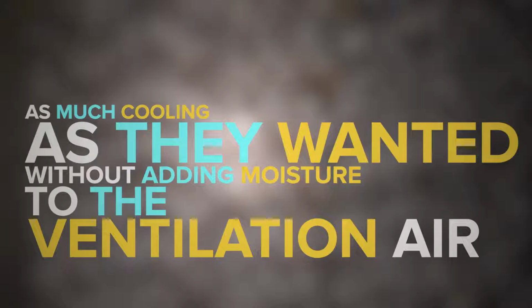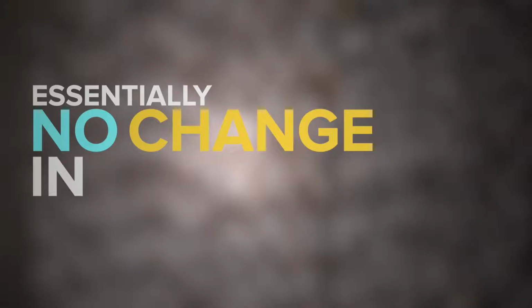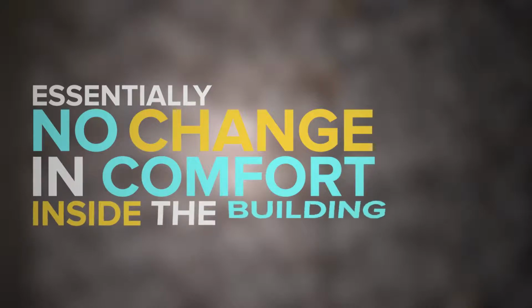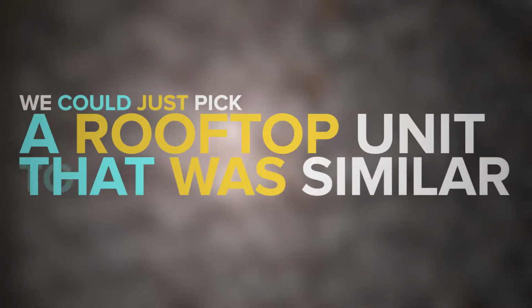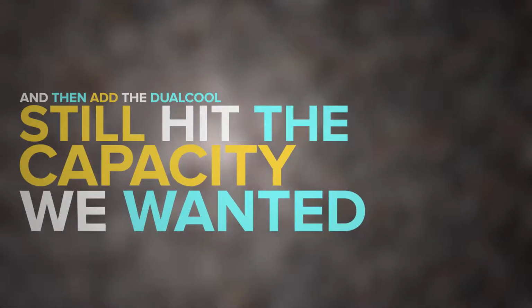The DualCool system with the new package unit made it so that there was essentially no change in the comfort inside the building, or it would improve it. We didn't have to worry about matching capacity or ventilation, because we could just pick a rooftop unit that was similar to the old one and then add the DualCool and get extra savings, but still hit the capacity that we wanted.